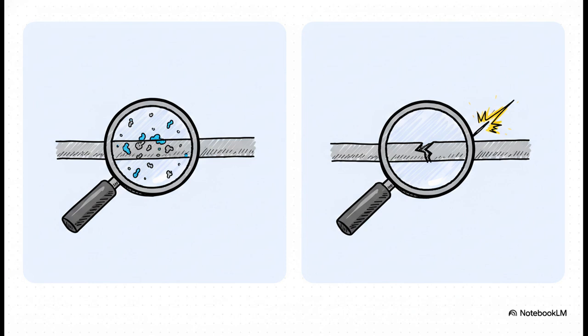The doctor, the IR test, its whole goal is about health. It's looking for signs of slow aging, like moisture creeping in over the years, or dirt building up. It is all about preventive care. The drill sergeant, though, is all about strength. The Hipot test is actively trying to find one single point of failure—a tiny nick in a wire, a defect from the factory, or spacing that's just a little too close that could cause a total breakdown under pressure.